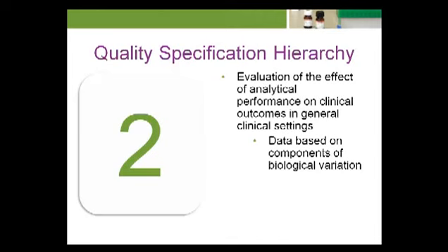The basic idea behind quality specifications derived from biological variation goals is to ensure that a shift in a test can be detected. We need to keep the analytical variation significantly smaller than the inherent biological variation of the test. Another approach is to interview treating clinicians and ask when they would consider a change in a result significant. Ultimately, this allows the construction of a set of quality goals. Unfortunately, this approach is very time-consuming, and the results vary from clinician to clinician.